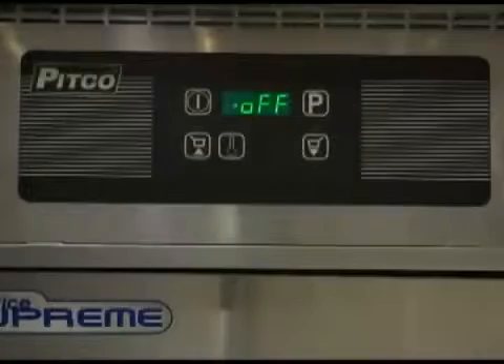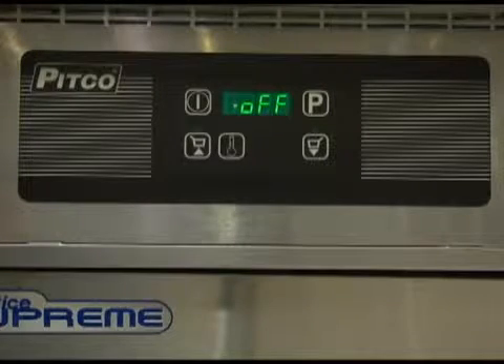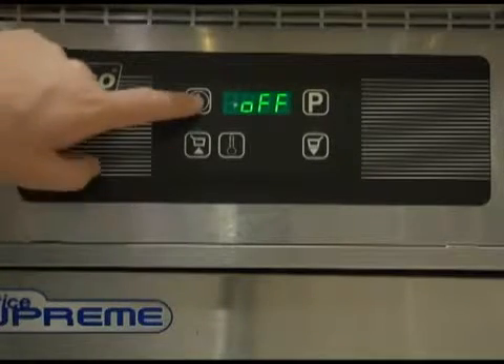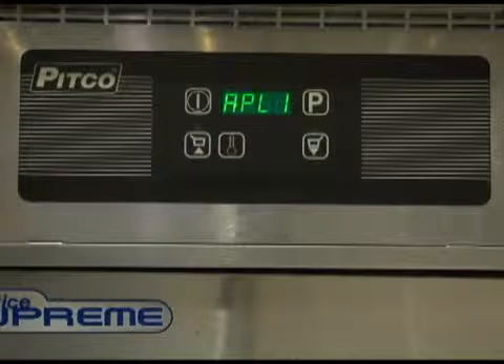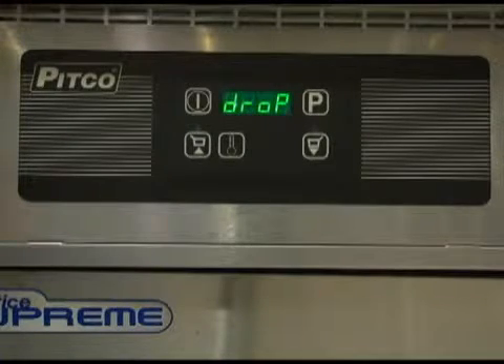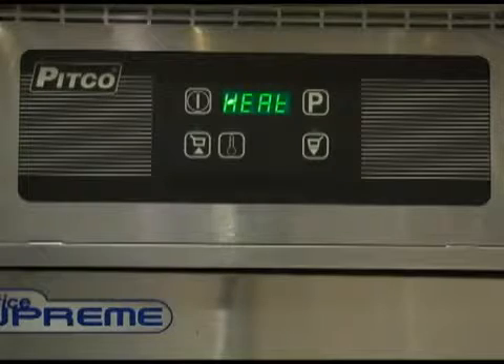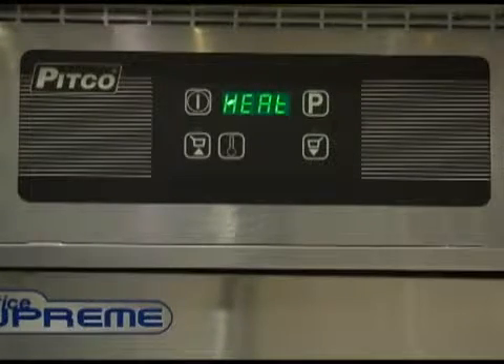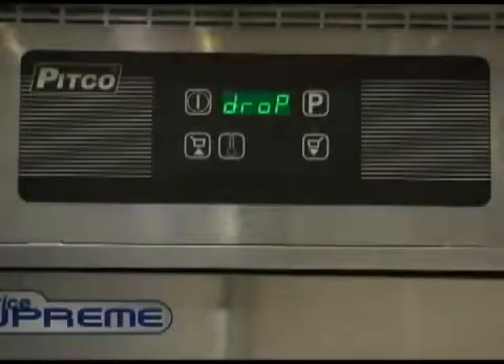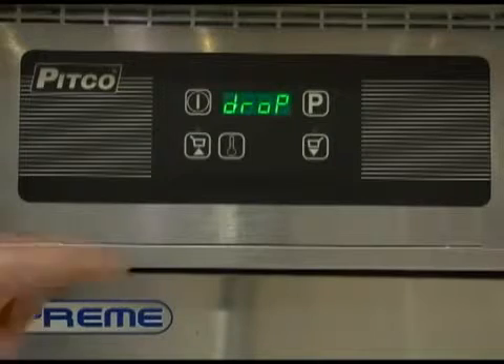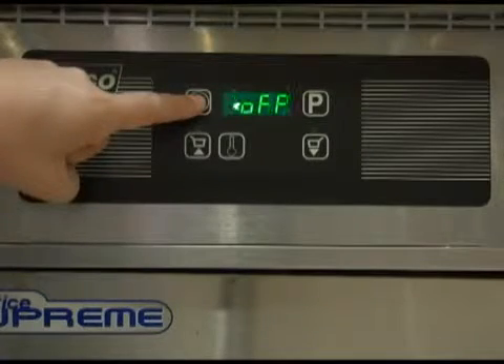To turn the controller on, press the power switch. The display will show for 2 seconds the current setting for the appliance type. We will review the appliance types later in the video. The display will then change to one of the normal operating displays of either drop, heat, melt cycle, or dashes if the temperature is below 150 degrees. To turn the controller off, press and hold the power switch for 3 seconds until the display shows off.